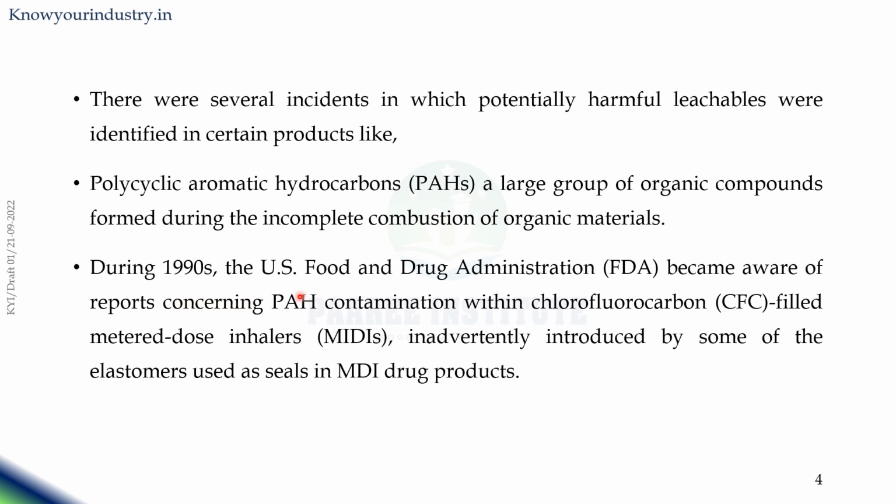During the 1990s, the US FDA became aware of reports concerning polyaromatic hydrocarbon contamination within chlorofluorocarbon filled metered dose inhalers (MDIs), inadvertently introduced by some of the elastomers used as seals in MDI drug products. This contamination was notified by the FDA during the 1990s.